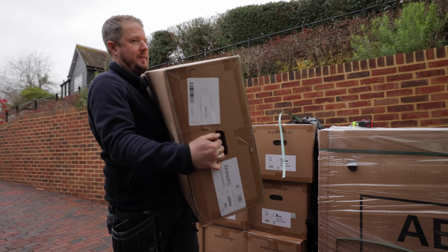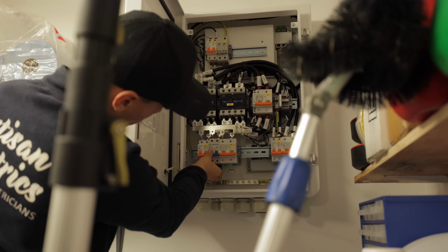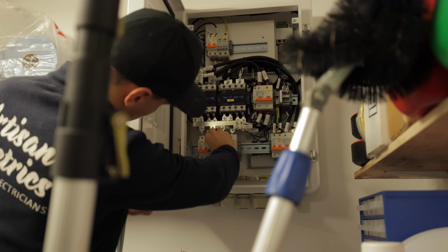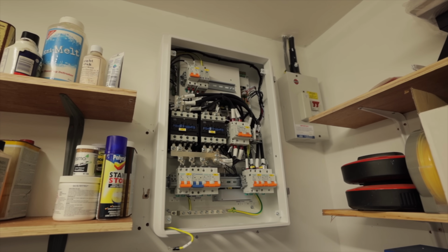A lot of systems have the capability to run in whole home backup mode, but they need a gateway, and that's crucial. Without that gateway cutting you off from the grid and switching you to battery storage, your normal home battery system simply won't work in a power cut, because all home battery inverters are grid tied and designed to cut off if the grid goes down.